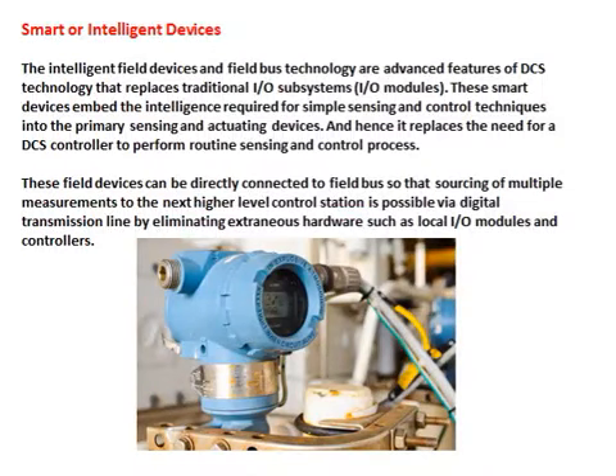Smart or intelligent devices. The intelligent field devices and fieldbus technology are advanced features of DCS technology that replace traditional I/O subsystems and I/O modules. These smart devices embed the intelligence required for simple sensing and control techniques into the primary sensing and actuating devices, and hence it replaces the need for a DCS controller to perform routine sensing and control processes. These field devices can be directly connected to the fieldbus so that sourcing of multiple measurements to the next higher level control station is possible via a digital transmission line, eliminating extraneous hardware such as local I/O modules and controllers.